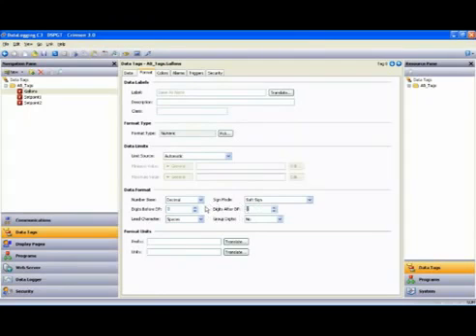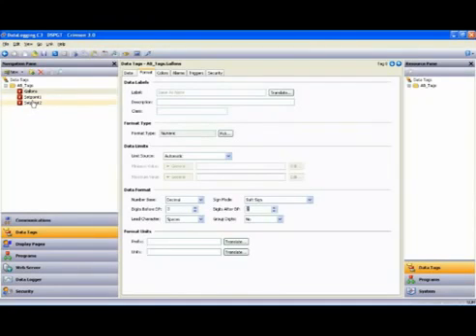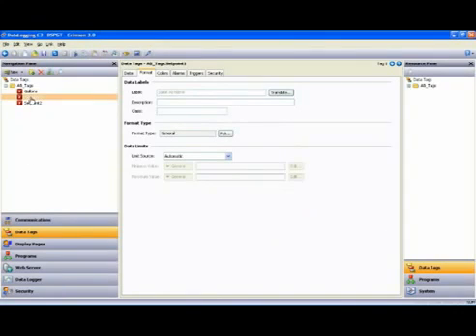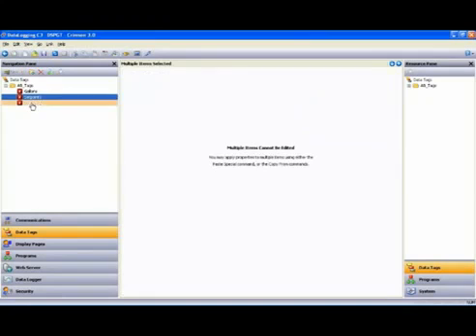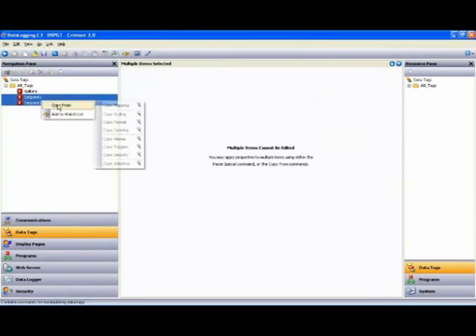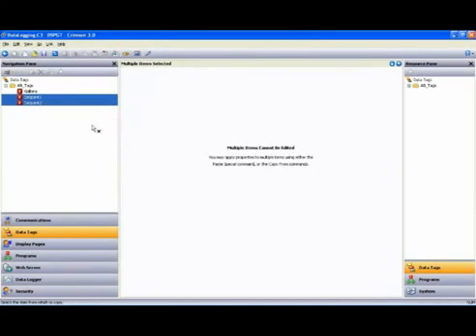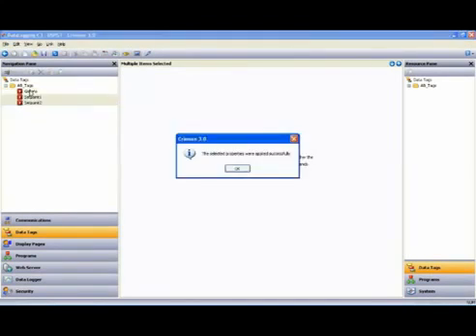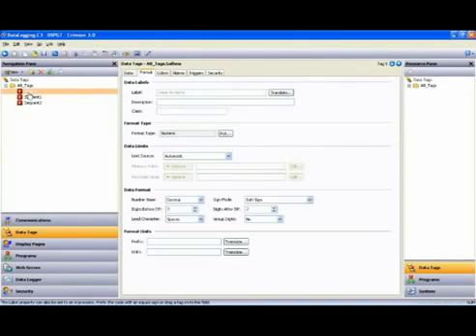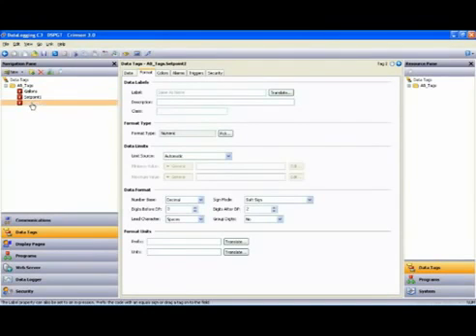Now, what if I want to change the formatting on the rest of my tags to match those changes? Not a big deal on two tags to do them one at a time, but what if I had 30 to change? Holding down my Shift key, I multiple-select the other tags, right-click on them, and select Copy Format. Now it's waiting for me to point at a source for the formatting. So I point at Gallons and click, and I'm told that the selected properties were applied successfully. And now if I look at each tag, you can see the formatting type and the data formatting has changed accordingly. A big time saver if you need to make changes to a long list of tags.